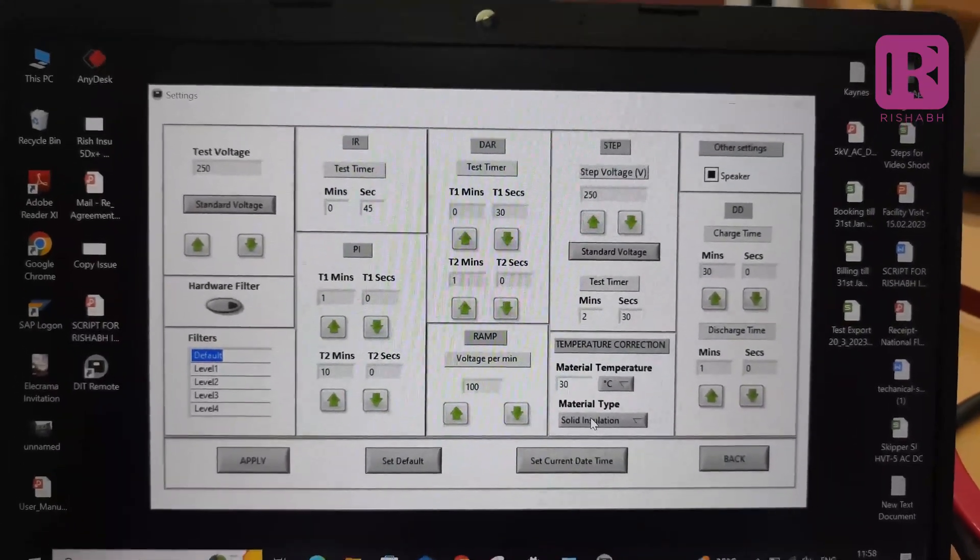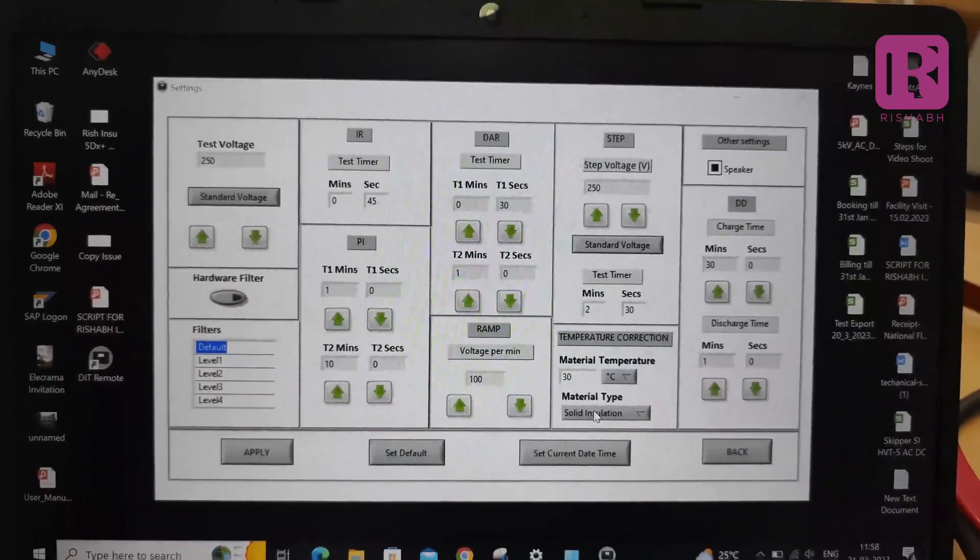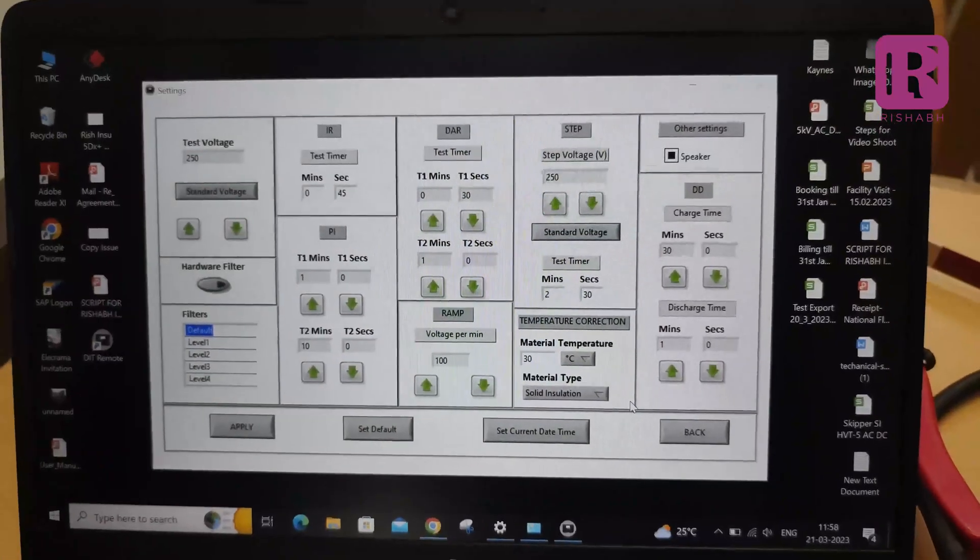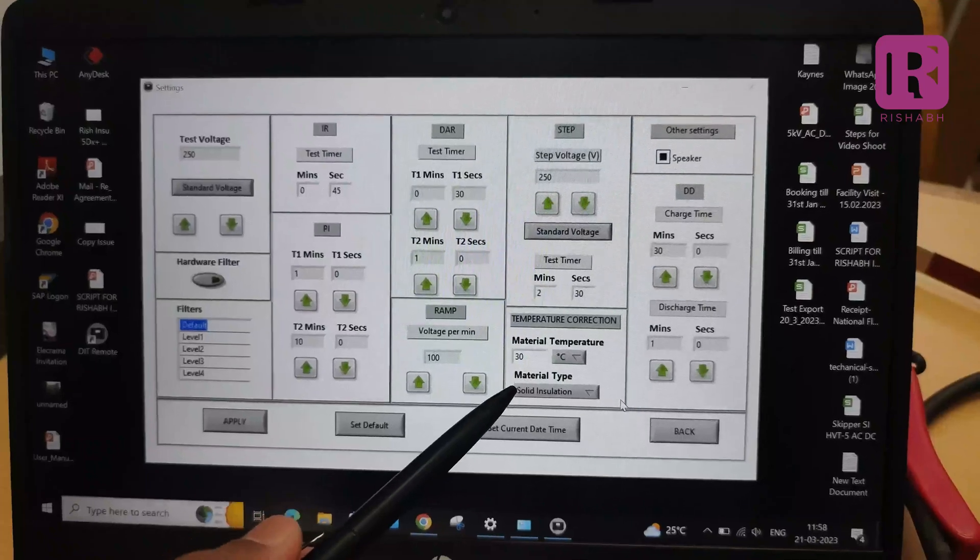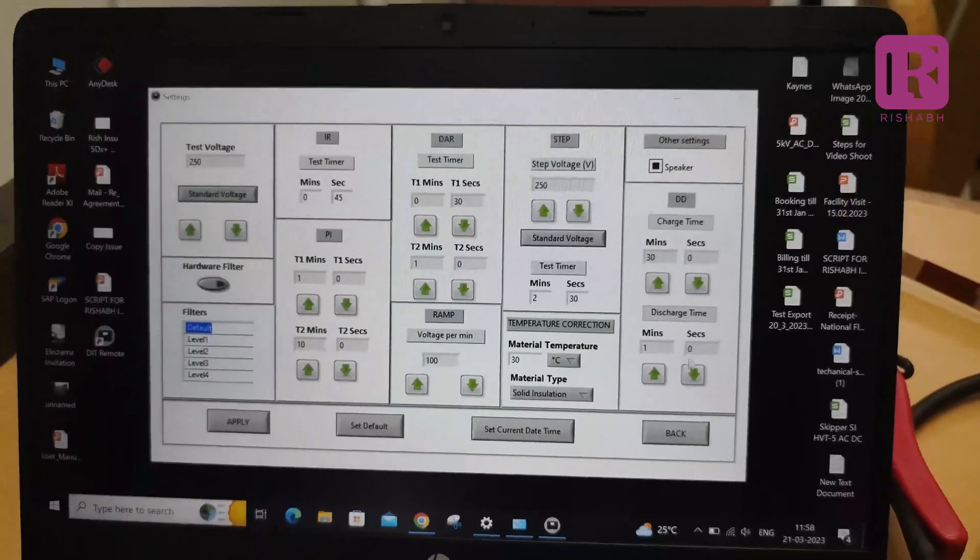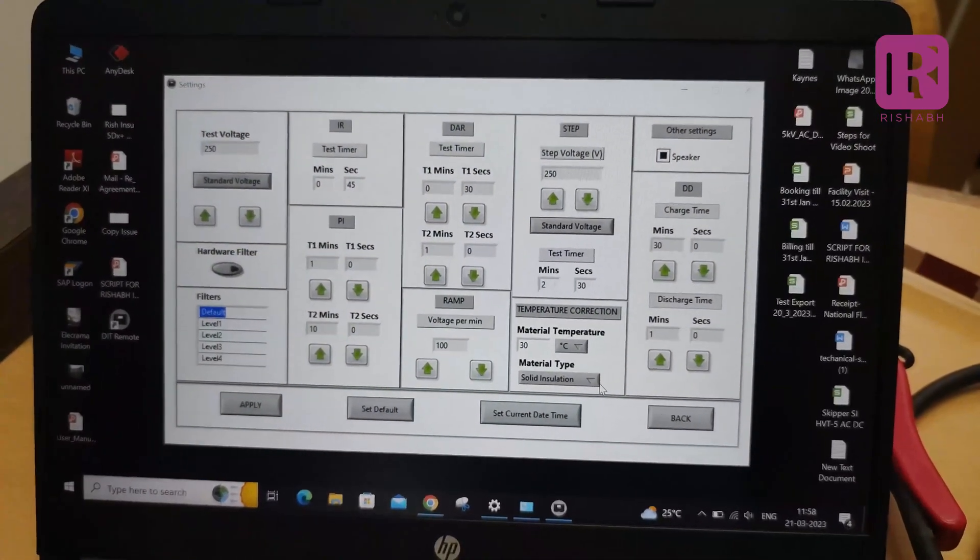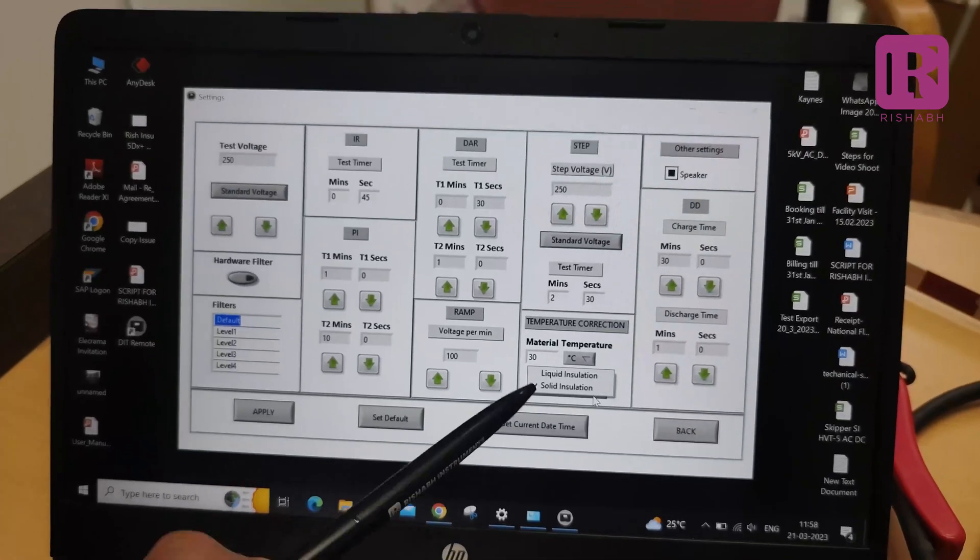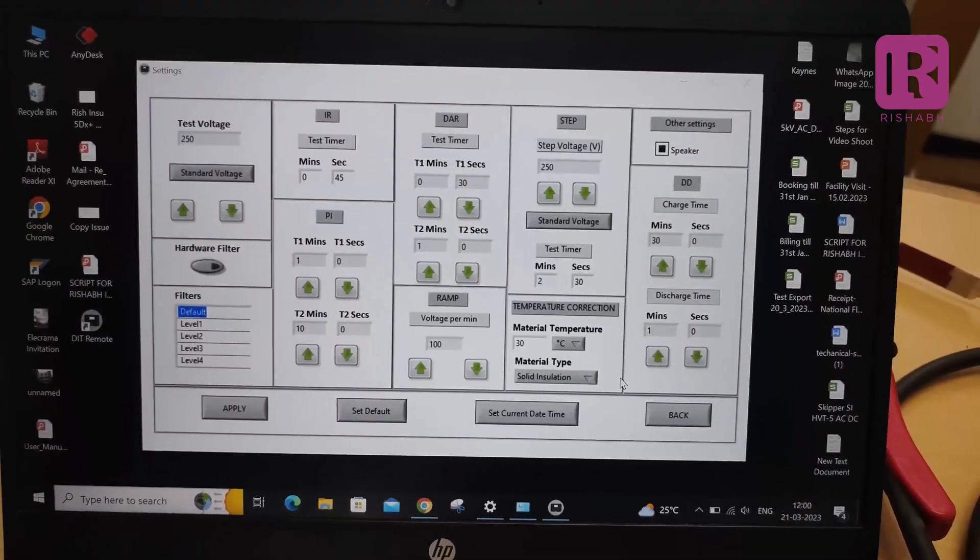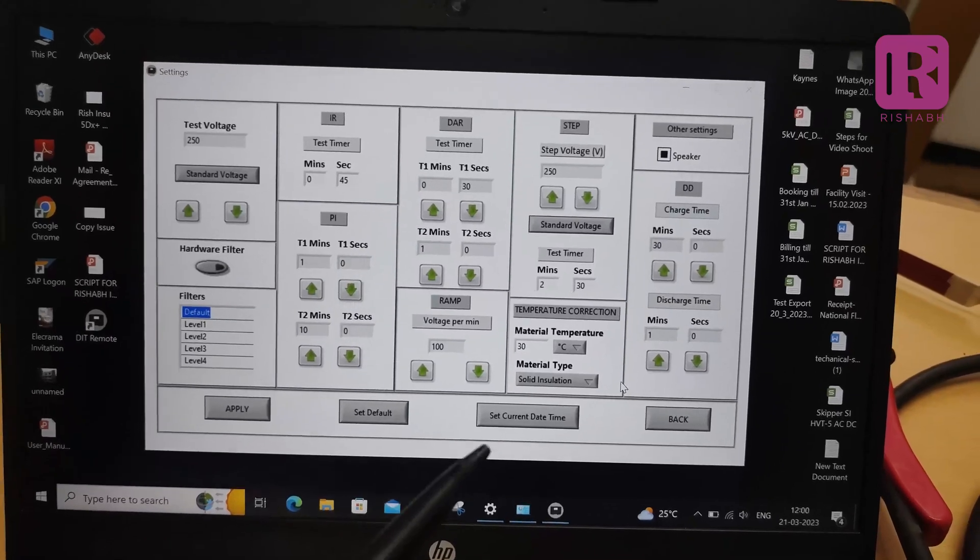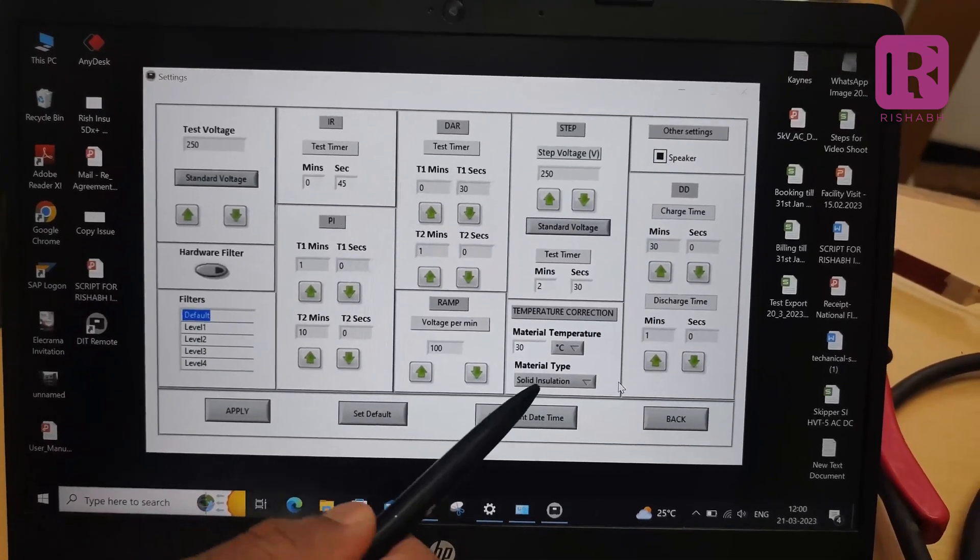In which IR value is corrected to 20 degree Celsius. As per this facility, you can set the material temperature in temperature correction tab for both solid and liquid insulation. I have set the material temperature 30 degree Celsius for testing solid insulation.